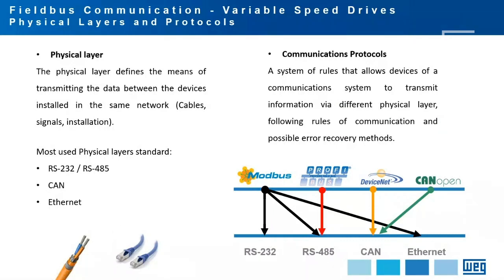Before covering the different communication protocols, it's important to understand two concepts: physical layer and communication protocol. The physical layer is basically the means of transmitting information from one device to another — how the signal will be transmitted, whether by cables, what kind of signal is used, and how cables are installed. The most common physical layers used in industry today are RS-232, RS-485, CAN, and Ethernet. The physical layer is essentially the hardware of the installation.